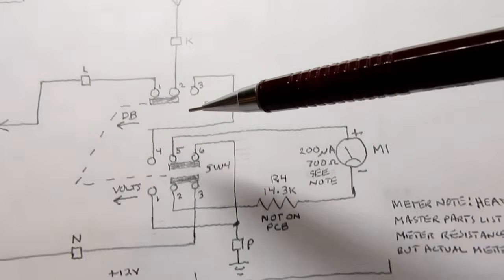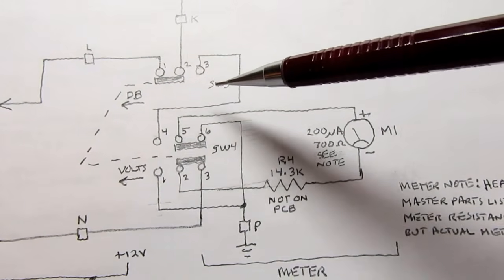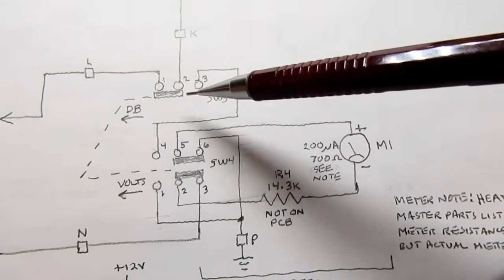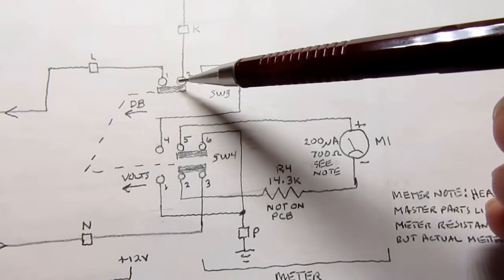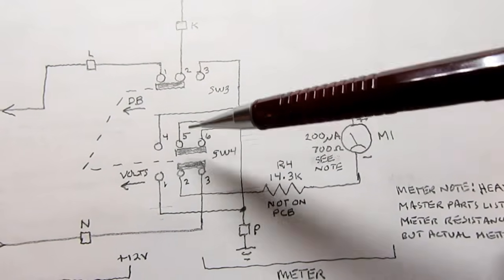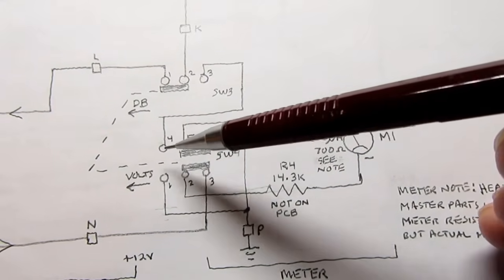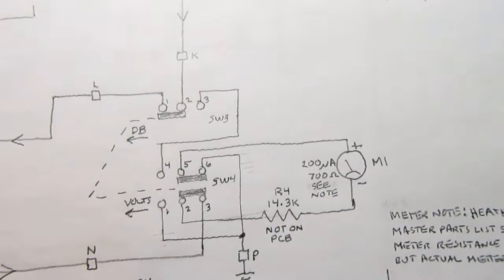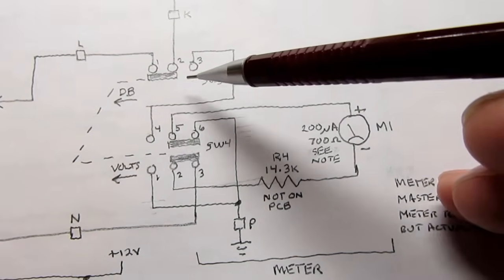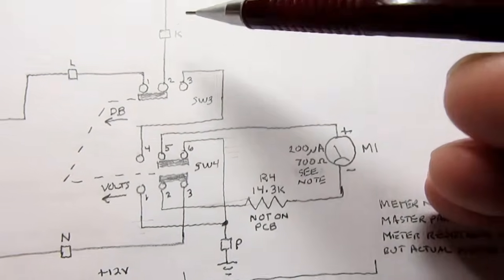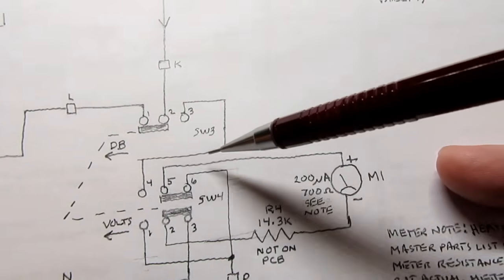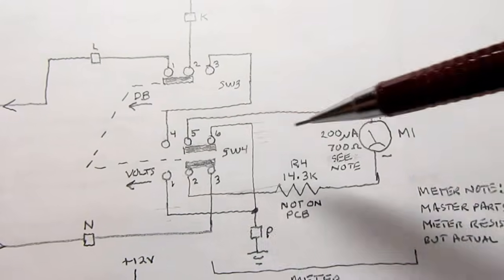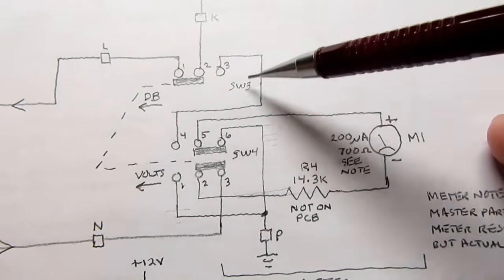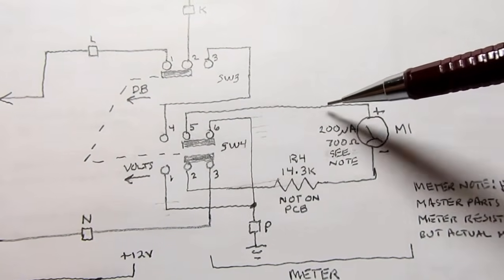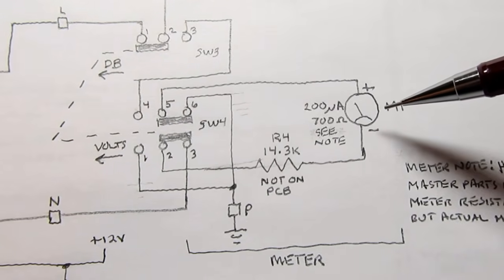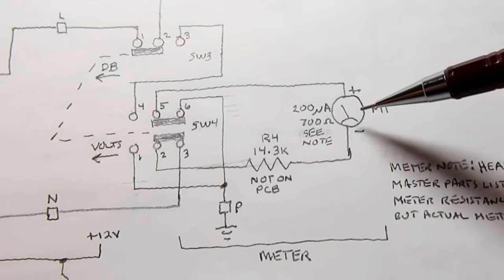We also have to drive the physical meter movement on the front panel. This is the dB push button on the front. This is the volt push button on the front. The switch is shown in the dB position with these 2 pins shorted out and these pins on the right shorted out. If you push the volt button, then these would shift over to here and here, and this one would shift over to here. But let's just say we're in the volt mode at the moment, so we have to visualize this slider being from here to here. That 0 to 3 volt signal is going to come through here, go around here, and because we have to be in the volt mode in order to read voltage on the meter, you have to visualize these two sliders as being here and here. So we come around here, we go through here, we come into the plus side of the meter, which is a 200 microamp meter movement. So 200 microamps going through it results in the meter reading a full scale deflection.